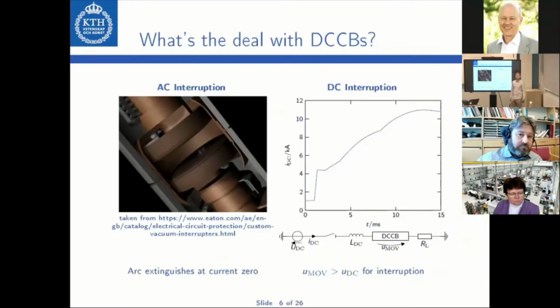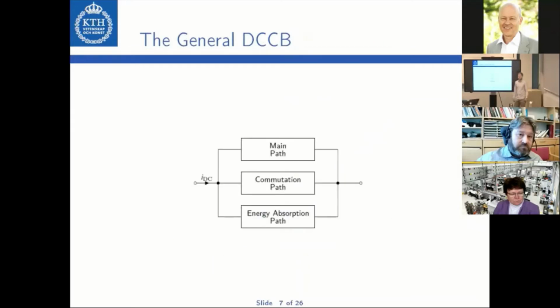Another option is to use a pure semiconductor-based solid-state breaker. For an HVDC system, hundreds of power semiconductors would need to be connected in series, and the semiconductors would then turn off the fault current. The thing is that these power semiconductors would also exhibit losses during normal operation, which would be unacceptably high. Therefore, a workaround is needed. This is the general DCCB structure, which you can see in this illustration. The general DCCB structure consists of three paths: the main path, the commutation path, and the energy absorption path.